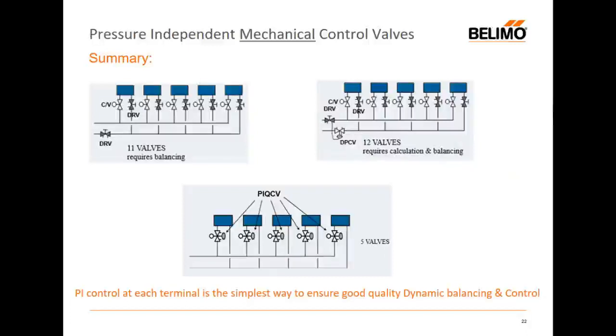When we summarize control solutions that we just looked at, we can say three things. We can say, yes, we recognize that conventional control valves have a role, but if they do, I've got to manually balance them. I've got to manually balance each of the circuits to ensure that each is getting their correct flow rate, and I can only do that in design. I've got to choose a control valve with some authority, so I've got to understand the resistance of the circuit, or at least the coil, so I can try to match it with my control valve.